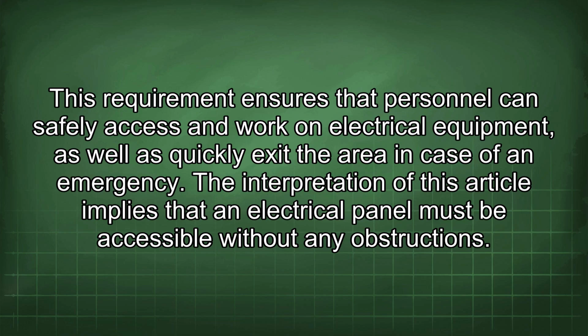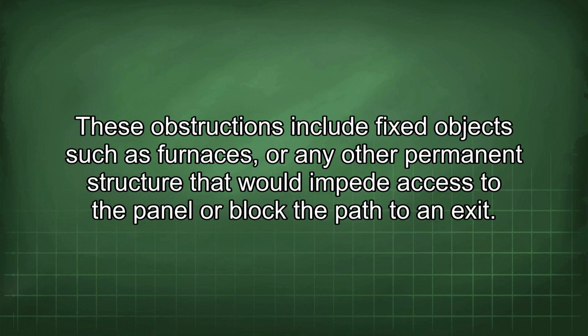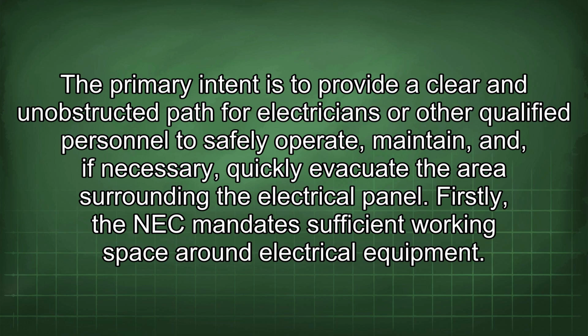The interpretation of this article implies that an electrical panel must be accessible without any obstructions. These obstructions include fixed objects such as furnaces or any other permanent structure that would impede access to the panel or block the path to an exit. The primary intent is to provide a clear and unobstructed path for electricians or other qualified personnel to safely operate, maintain, and, if necessary, quickly evacuate the area surrounding the electrical panel.